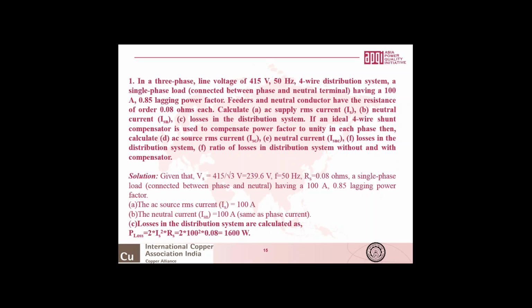Given that we have a line voltage of 415, the phase voltage will be 415 by root 3, that comes to 239.6 volt, and the frequency is given as 50 hertz, and the feeder, or you can call it the distribution cable, resistance is given as 0.08 ohm, and a single phase load connected between phase and neutral having 100 ampere, with a power factor of 0.85 lagging.